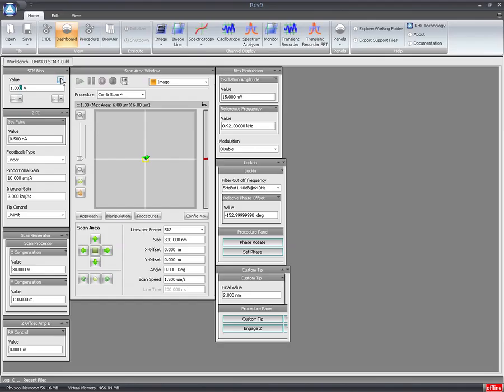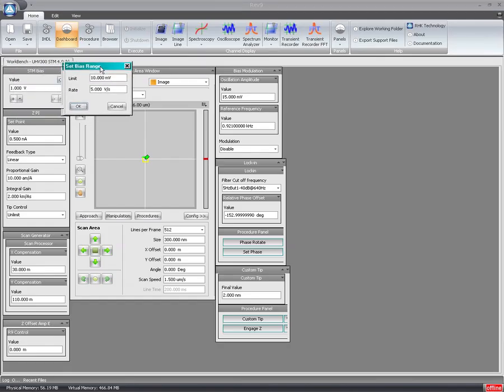With the SPM 1000, you could change how fast the control changed by how fast you turn the knob. Well, we don't have knobs in the R9, but we do make it very easy for you to control how fast a value is changed. Almost every value that can be changed in the R9 has a parameter called rate. For the bias, we have it set here to 5 volts per second. So no matter how fast you change the front panel, it will never move faster than the 5 volts per second.